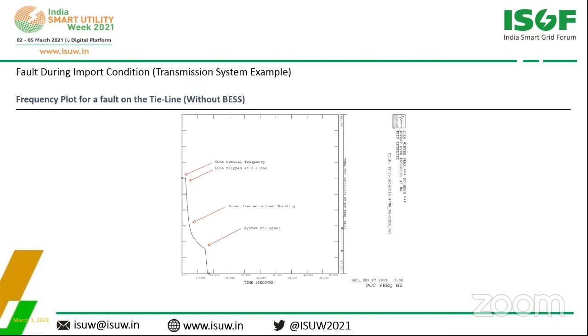This plot shows that when there's a loss of the tie line, the megawatt deficiency in one part of the island results in frequency collapse, even with under-frequency load shedding and other preventive actions in place to regulate frequency.